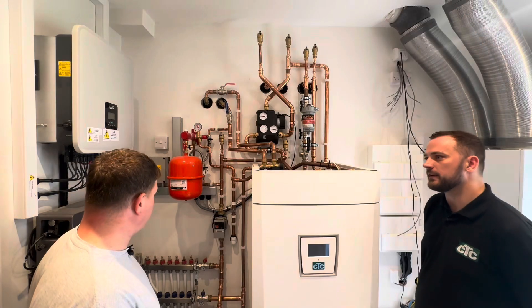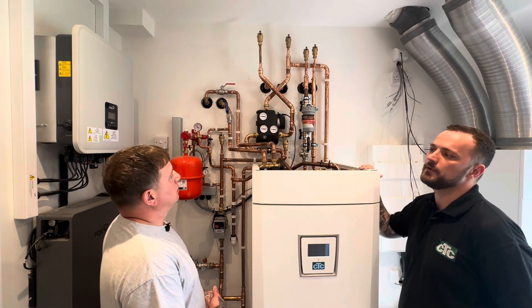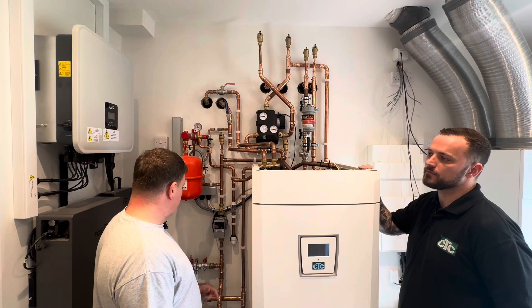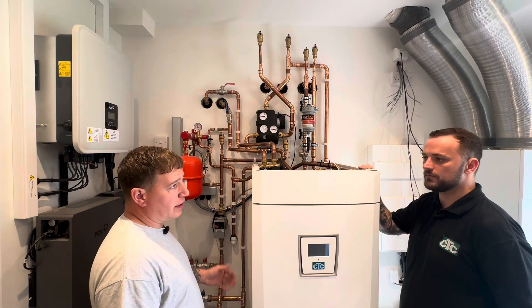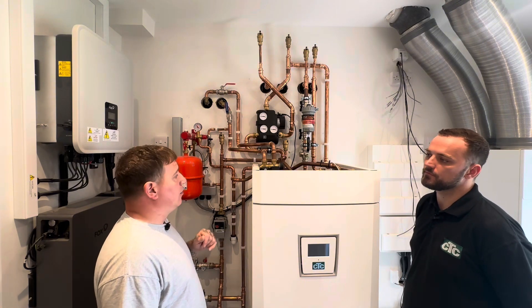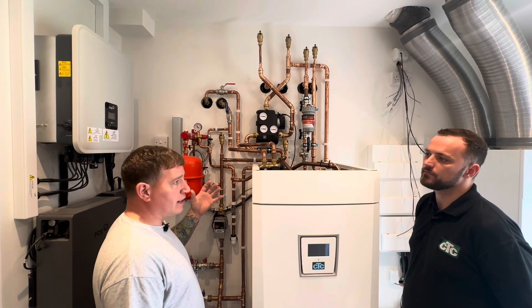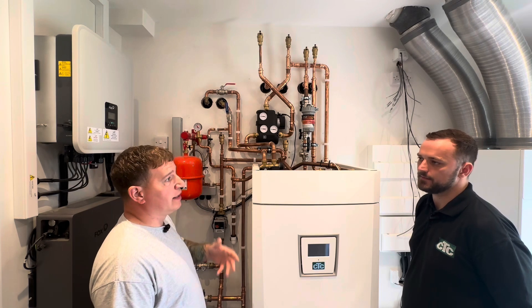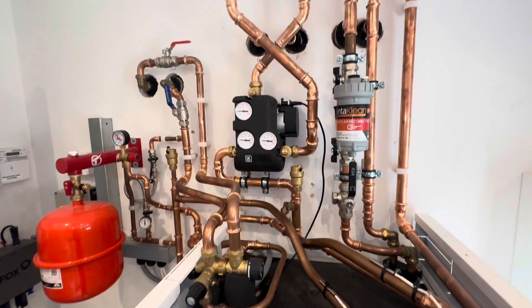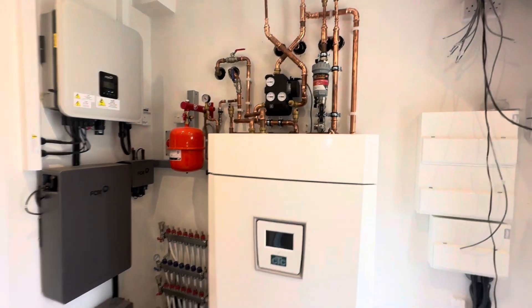What temperatures would you expect the system to produce to heat the house to 21 degrees internally? Underfloor heating is low temperature — we've designed it as low as we can, at a 42 degree flow temperature, but that's when it's nearly minus four outside. So it has to be really cold for it to run that high. The heat pump is weather compensated — based on the outdoor temperature it modulates the flow temperature down as low as possible to maintain a 21 degree indoor design temperature. I'd expect this system to be running around 36 degrees for 80% of the heating season.